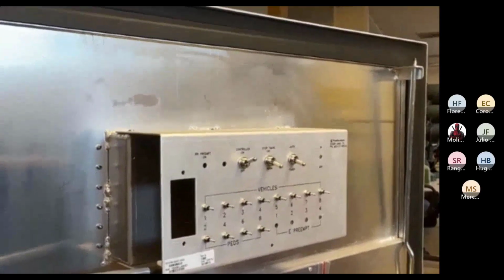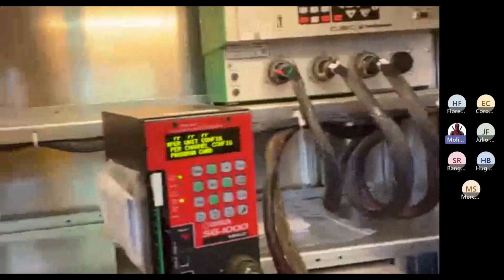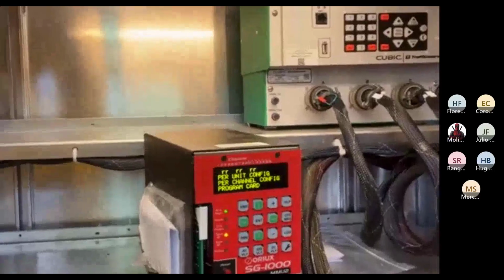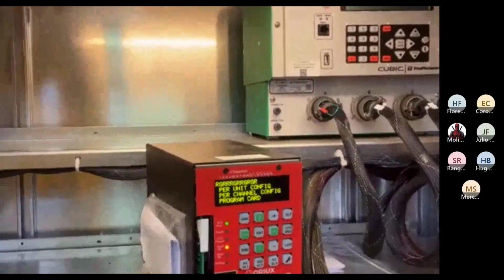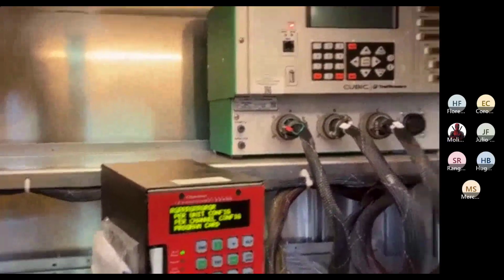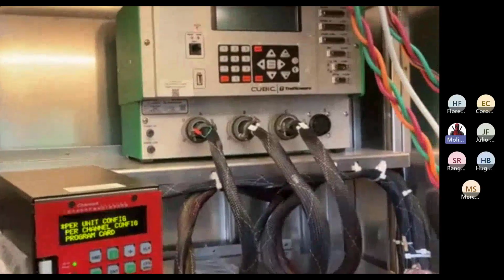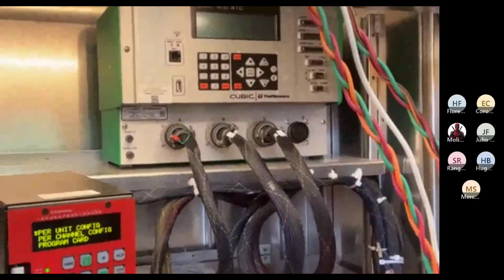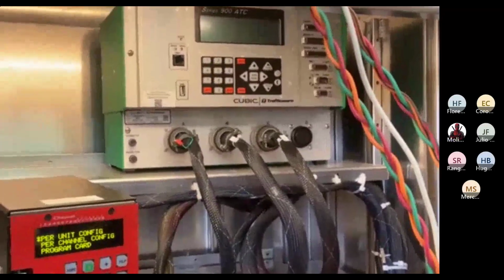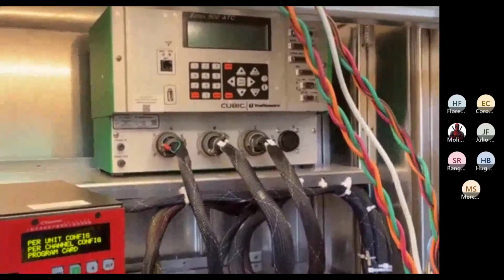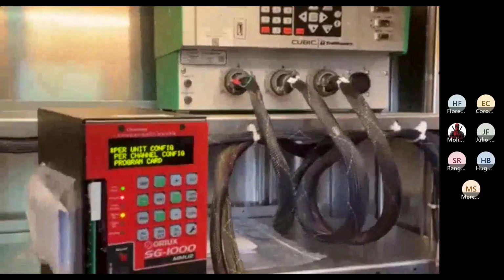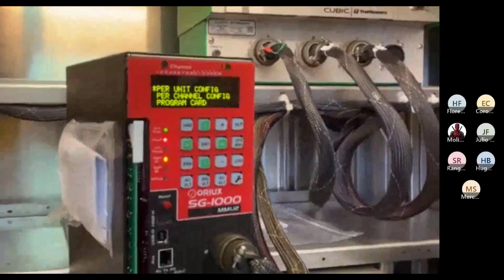Hold up. So the cabinet flash, I need to know how that cabinet flash is wired. That's the controller. I turned the controller off, and it still didn't come on. It's giving me the red light flash, but that's not coming on. Maybe. Wait, do you have a flash switch on the police panel? Yes. Flip that one, see what happens. That may be wired to local flash. Oh, well, you have to turn the controller back on.